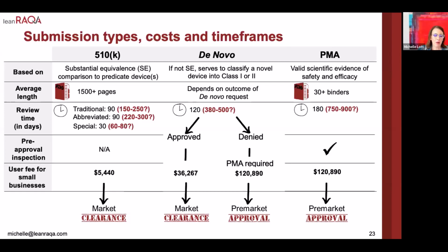The 510K process, I think, the whole review time based off of the classification risk is another big difference in what to expect when you compare this to the MDR technical file review specifically. The FDA clock time for 510Ks is generally 90 days, and they're running right around 200 days, regardless of the type of device that you're having reviewed.